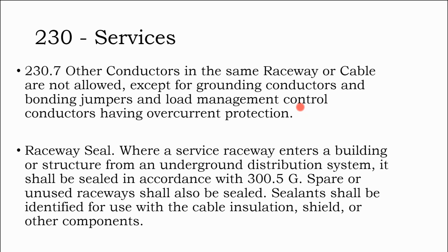But then you might find a situation where, okay, I'm doing this solar battery and I also want to power up the weather monitoring station. Do I have to keep that outside the gutter that I'm putting all this cable into? The answer is no. Code does give a little bit of allowance for other devices related to energy management, and control circuits associated with energy management.